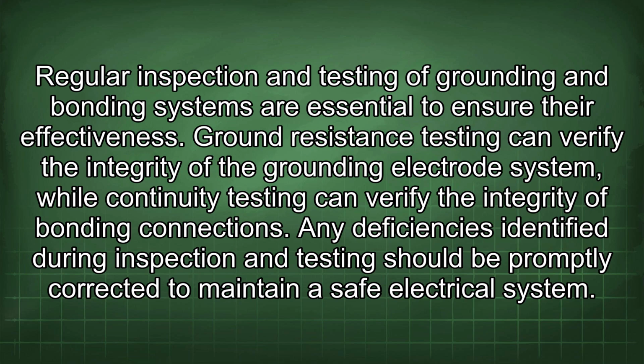Regular inspection and testing of grounding and bonding systems are essential to ensure their effectiveness. Ground resistance testing can verify the integrity of the grounding electrode system, while continuity testing can verify the integrity of bonding connections. Any deficiencies identified during inspection and testing should be promptly corrected to maintain a safe electrical system.